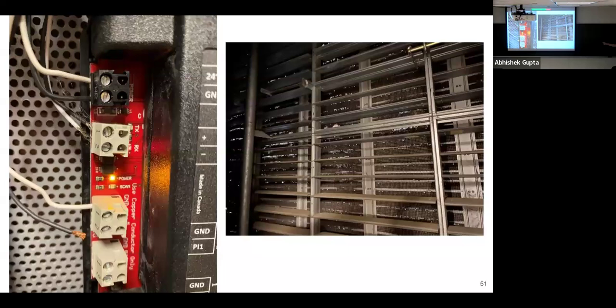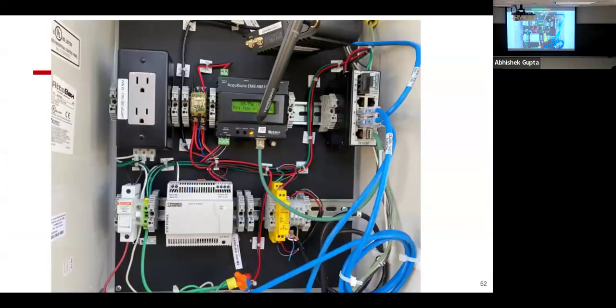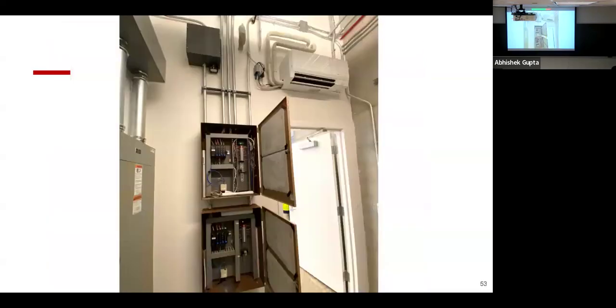Here, obviously, we have some poor connections, loose wires on this one. Here we have the outside air damper — they're completely blocked with debris. And we already talked about this one; this is another example of a cell modem up at the top there, hidden into a control cabinet.